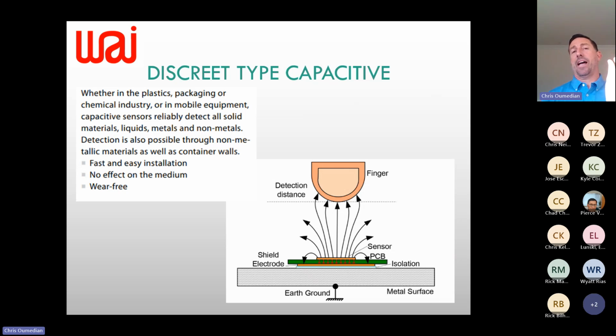So if you've got a thin plastic container that it's on, and let's say the dielectric constant of that poly is 1.5, and you've got some sludge that's got a dielectric constant of, I'll make a number up, 10. As that level goes above where the sensor's at, it's going to trip off. So you're only going to get, I'm at this point on the level. A lot of these applications are going to be a high warning, a low warning, and maybe you've got something in the middle. Some folks will sort of array them to get 3 or 4 readings out.